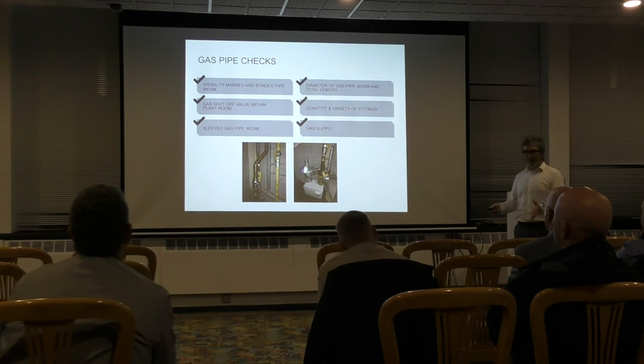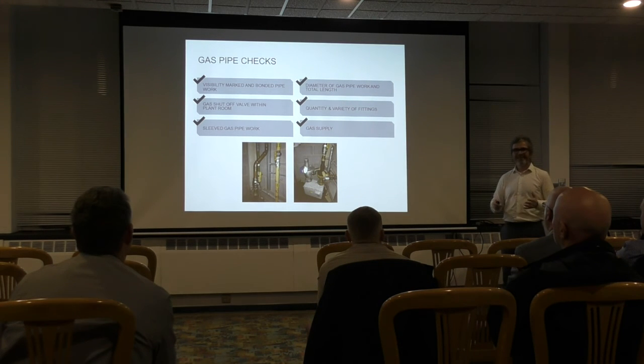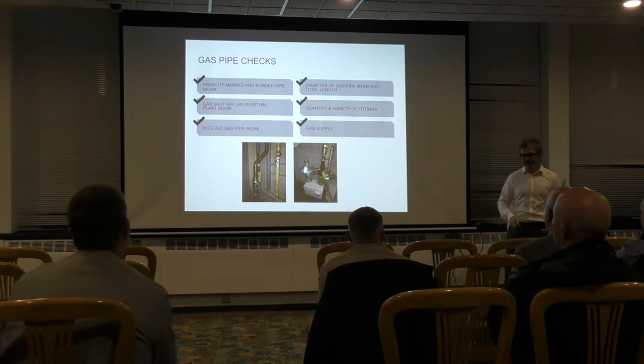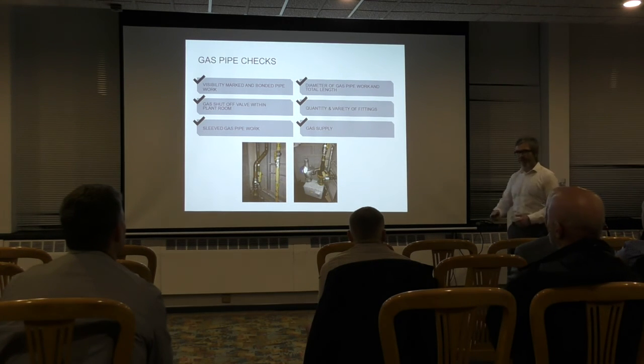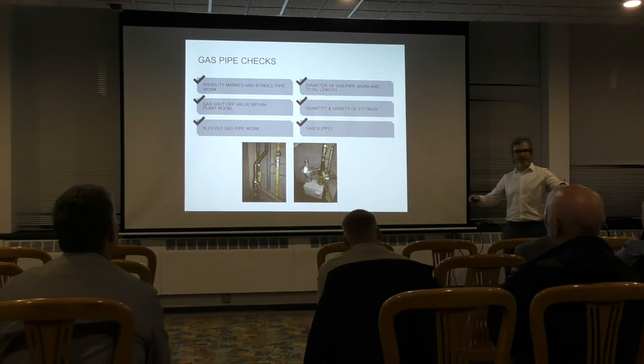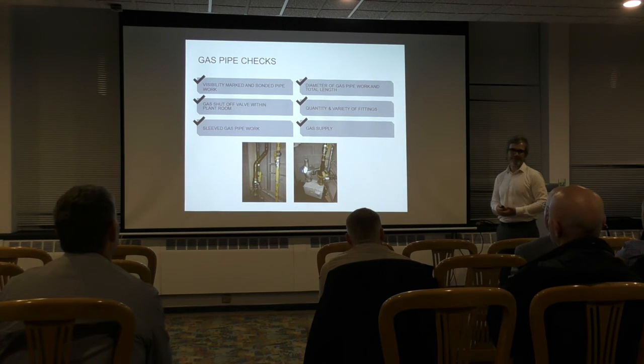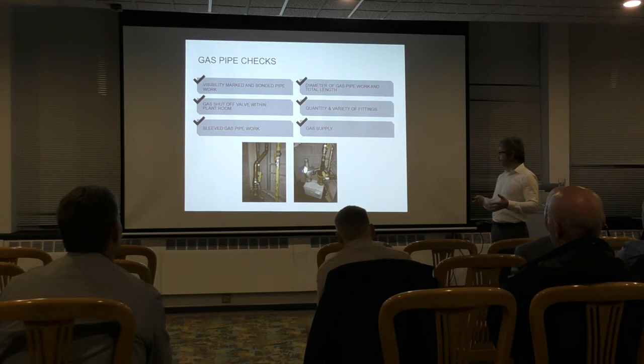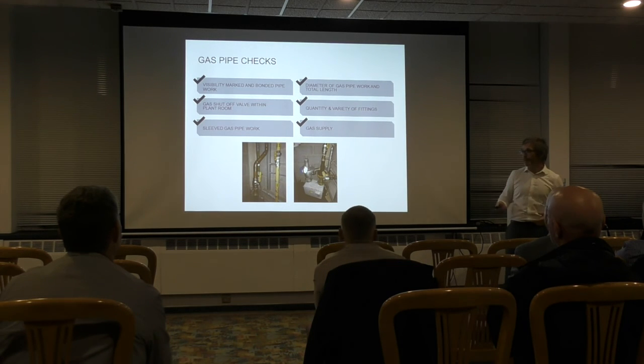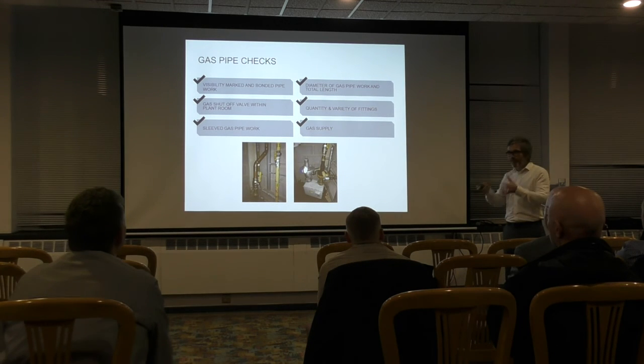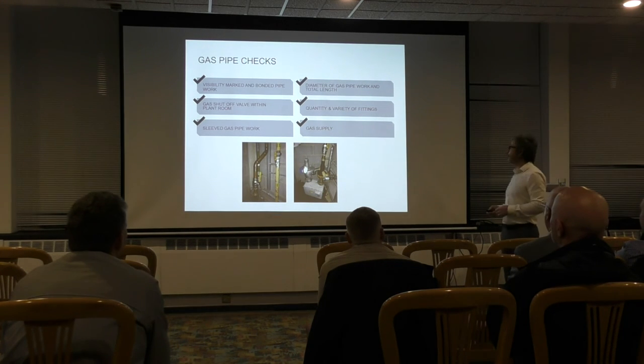And what I would always say is that older boilers are far less sensitive to gas pressures than newer boilers. And what you don't want to do is walk into that plant room and think, well, okay, my boilers are sitting there, they're working fine, the gas pressures must be fine. I'm not going to fiddle around with the gas pipe. And then you take those boilers out, put some nice shiny new condensing boilers in, and all of a sudden we've got gas pressure problems. Chances are those boilers have been sitting there running on 10 millibar gas pressure, where your new boilers now, probably minimum 15 or 17 millibar. So just be aware of that and make sure it's adequate for what we're proposing to put back in.